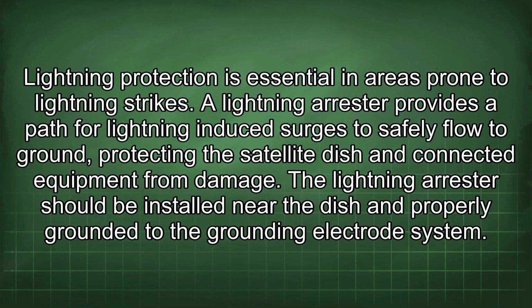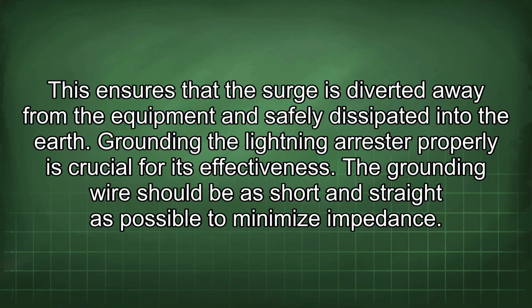A lightning arrestor provides a path for lightning-induced surges to safely flow to ground, protecting the satellite dish and connected equipment from damage. The lightning arrestor should be installed near the dish and properly grounded to the grounding electrode system. This ensures that the surge is diverted away from the equipment and safely dissipated into the earth.